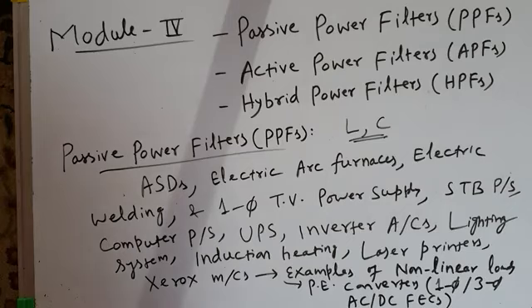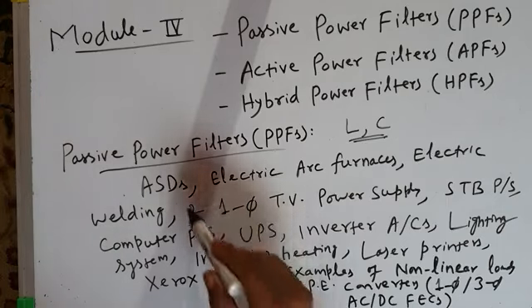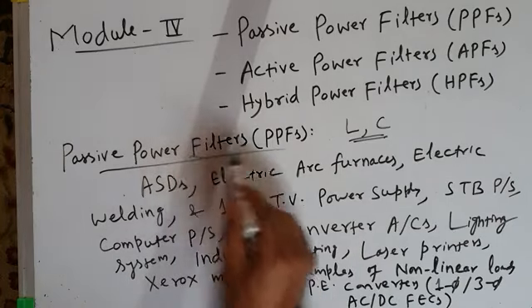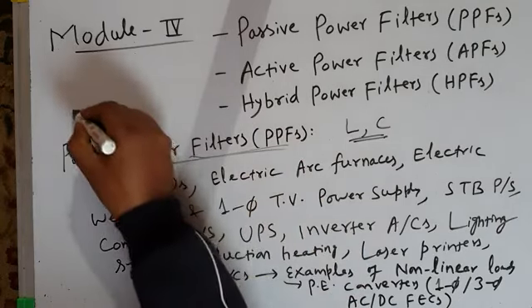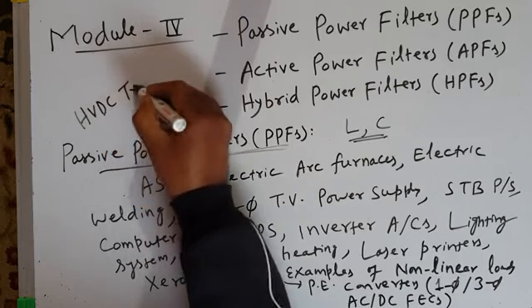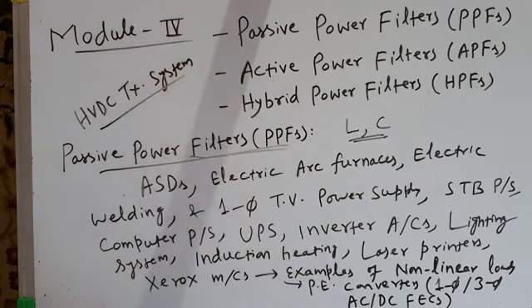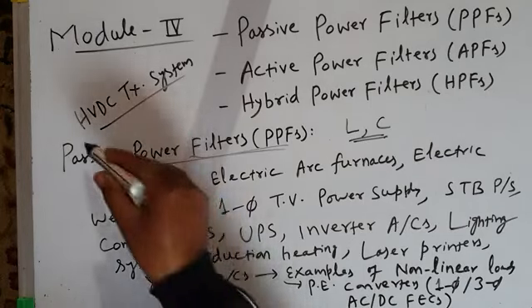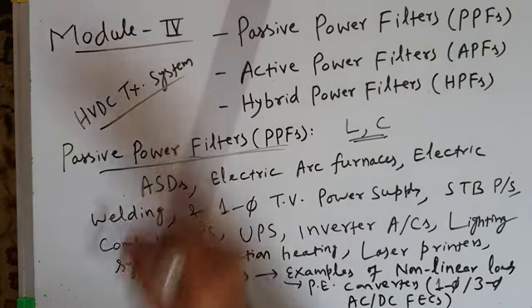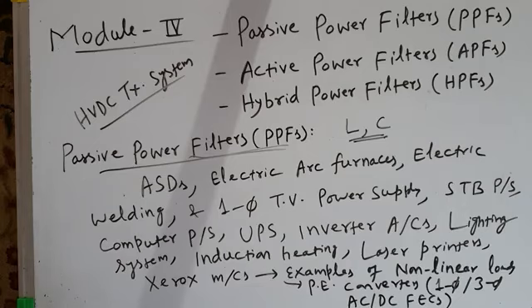Passive filters have tremendous applications in low to medium power applications and are very popular there. In high power applications, passive power filters are very popular in HVDC systems (high voltage direct current transmission systems). The primary objective of passive filters is harmonics compensation or cancellation, and some reactive power compensation also.